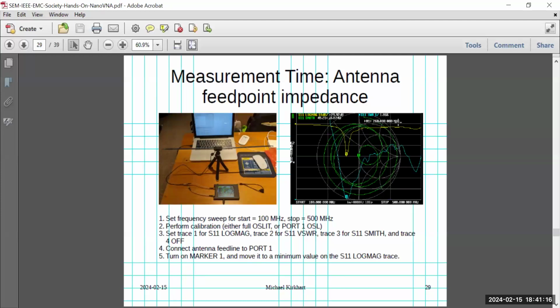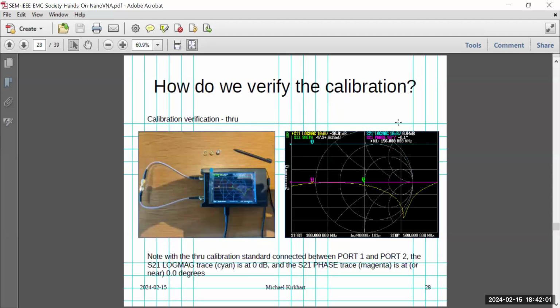Oh, yes, you have a question? I was expecting with the calibration for the logarithmic S11 to be flatter. S11, yeah, well, again, when you get an S11 log mag below, say, 20 dB, that's a pretty close match. And now you're starting to see the imperfections in the system, potentially in the VNA, but probably this has more to do with the calibration standards and the cable and all that kind of stuff. Remember, the default is 10 dB per div. So no, it doesn't show you that. And this is adjustable though.